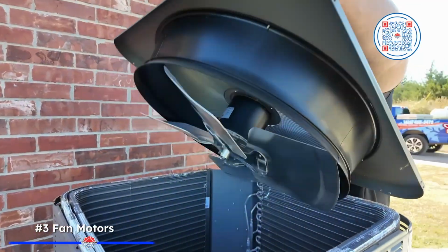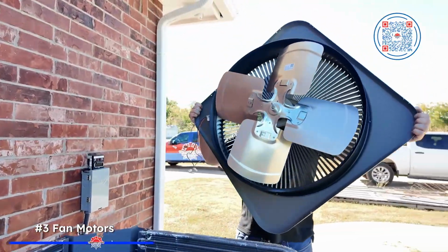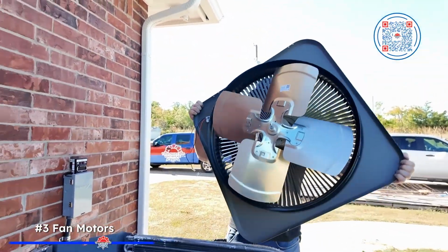What we see on fan motors a lot of times is that the fan motor has gotten hot at some point or another. We can tell this because there is a sealed bearing pack inside the blower motors and the condenser fan motors. If it gets hot, that sealed bearing pack begins to leak the grease, and that grease can be seen around the rim of that fan motor.